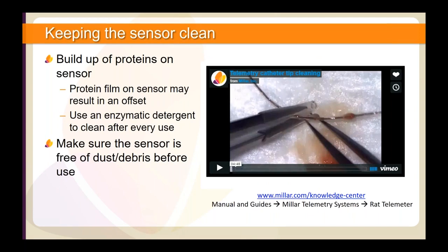Dirty sensors are the main cause of pressure offsets, so it is very important to ensure that the sensor is free from protein deposits and dust and other debris every time you use it. Never put a dirty sensor away thinking you'll clean it properly next time. It becomes very hard to clean once it dries. Before each use, inspect the sensor under a microscope and carefully wipe away any dust or small fibers that may be visible. Even a small amount of dust or fibers can cause an offset.